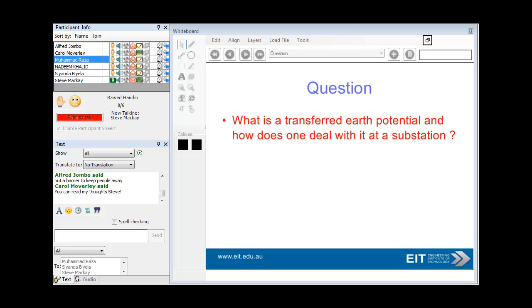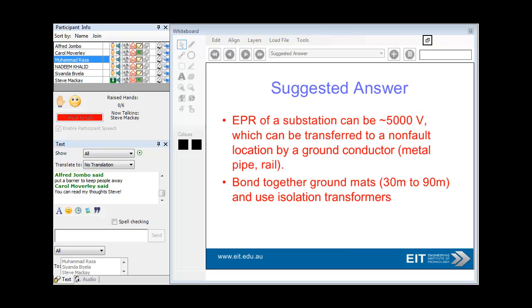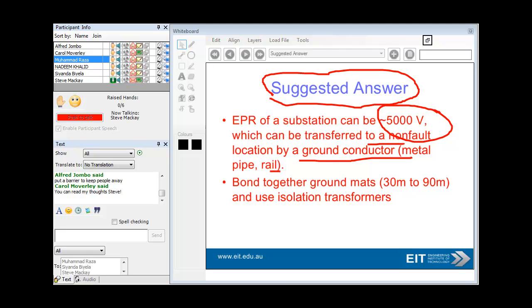Here's a suggestion: earth potential rise at the substation can be about 5 kilovolts, which can be transferred to a non-fault location by a ground conductor or metal pipe rail. Probably the best solution is to bond together the ground mats and use isolation transformers — this addresses earth potential rise due to an electrical fault.